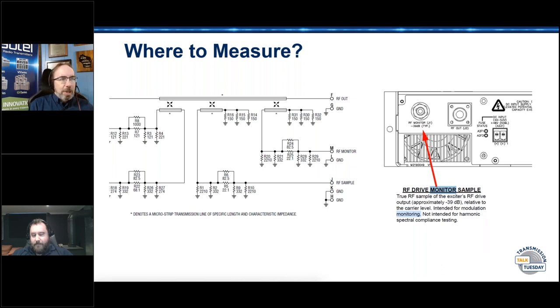Yeah. So the best place, and we'll touch on it on the next slide too, the FCC for AMs specifies with an antenna a kilometer away. So sometimes your local regulatory authority will tell you where you're measuring this stuff. If you're looking for harmonics or cabinet radiation, obviously you're not looking at a port right off the filter. In that case, you're going to have an antenna and be measuring with a directional antenna.